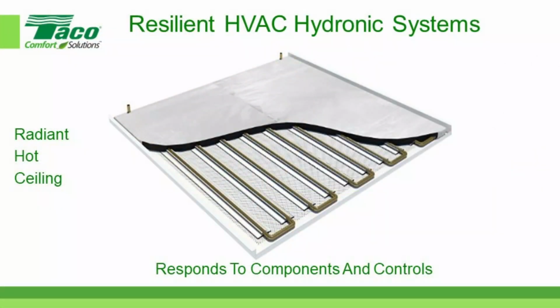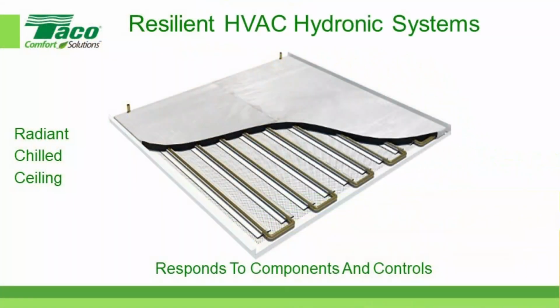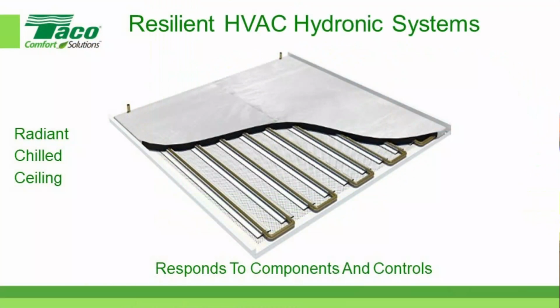These are radiant ceiling panels, and they've been used for a very long period of time for heating. We circulate hot water through these radiant panels that mount in the ceiling of a building. We typically use them on the perimeter of a building, and so we can easily heat the building. And the other application for the exact same component is radiant chilled ceilings. If we circulate chilled water above the dew point temperature, we can remove sensible heat at the perimeter of the building and use radiant devices. So if a building has existing radiant heating panels, they can also be utilized to provide radiant cooling, as long as your control system is sophisticated enough and your fluid delivery system is sophisticated enough to make sure that the water temperature is always above the dew point temperature.